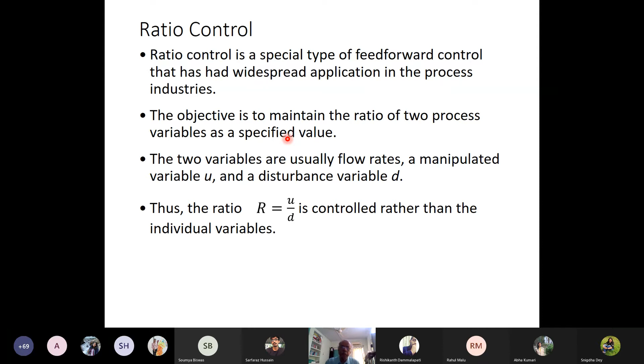So this is basically the case where, let's say, this is the disturbance stream D and this is the manipulated stream U. In this case, we measure the disturbance stream. We also measure the manipulated stream. We have a divider over here which calculates the ratio, which is the measured variable for this controller. This RM will go over here, and then this ratio controller will control the flow rate of the manipulated stream based on some ratio set point.